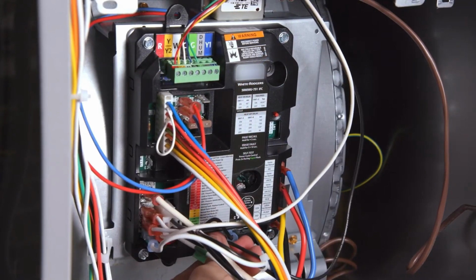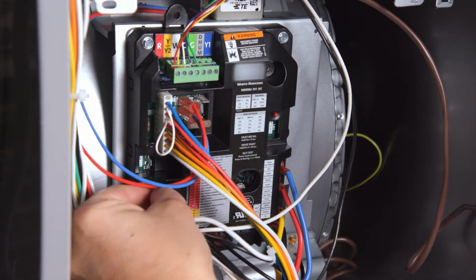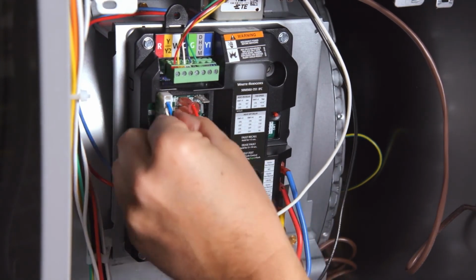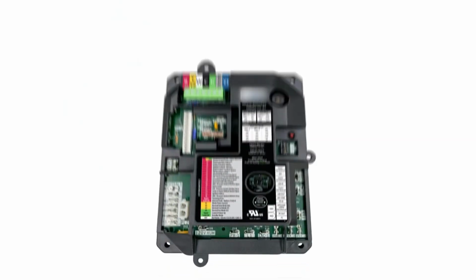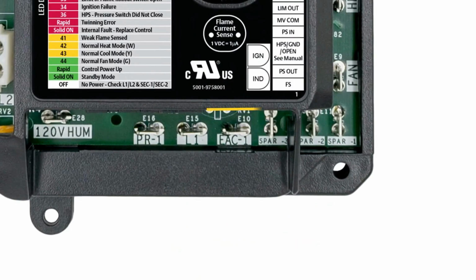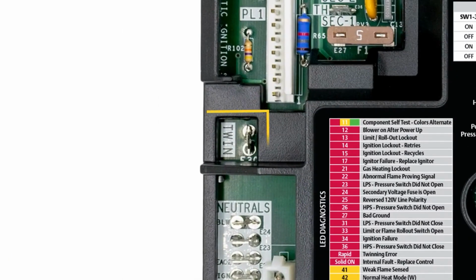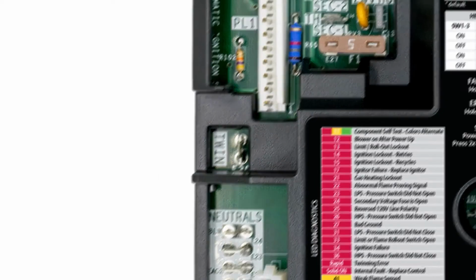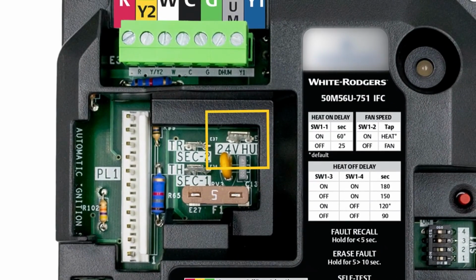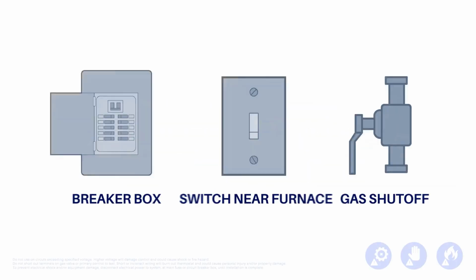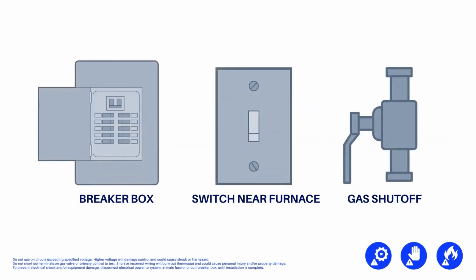Ensure all wires are secured to the control board and unused blower speed wires are attached to the spare terminals. This control also features a 120-volt electronic air cleaner accessory terminal, twinning terminal, and a 24-volt humidifier terminal. The system is now ready to be tested. Reconnect the electric power and gas to the unit.